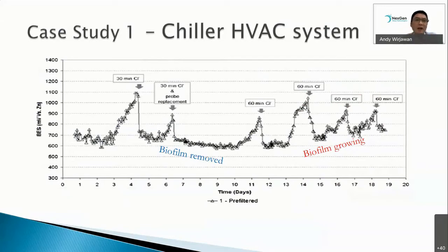Because a lot of the time we take a sample from the body of the water, so by monitoring the bacteria in the water itself, by taking a sample from the cooling tower and doing a total aerobic plate count, we then try to correspond it to the biofilm. But as you can see, the continuous dosing to the body of water in the cooling tower system can probably maintain the bacteria at an acceptable population. In Singapore, NEA requires a total bacteria population of less than 100,000 colony forming units per mil of water. As long as it is less than 100,000, it is okay from a public point of view and fulfills the NEA regulation.